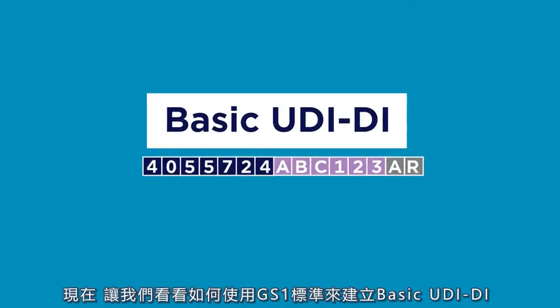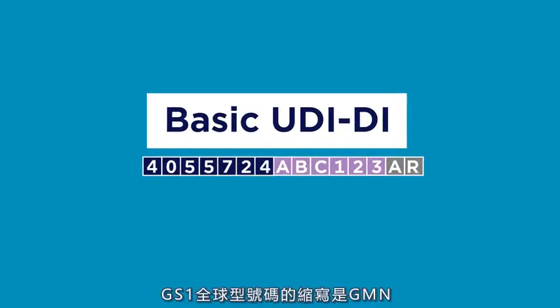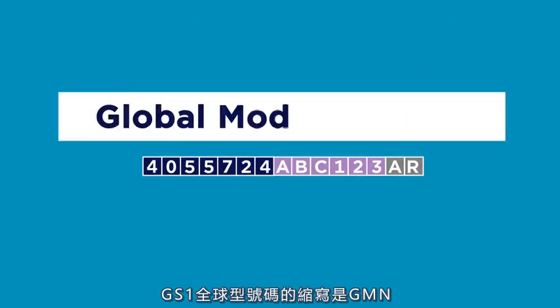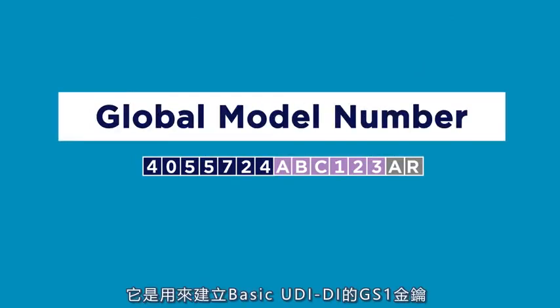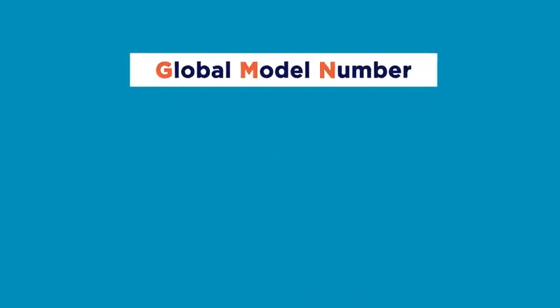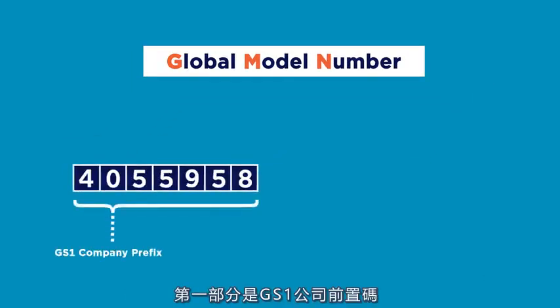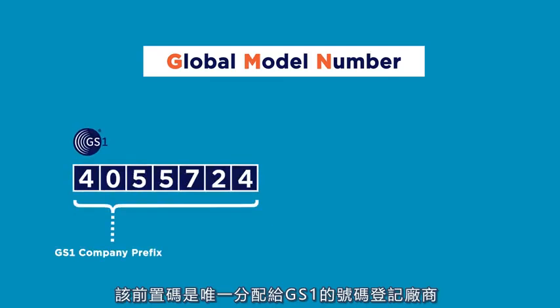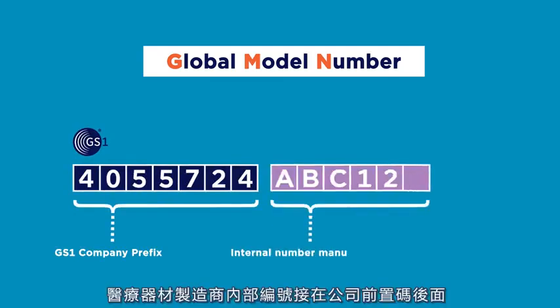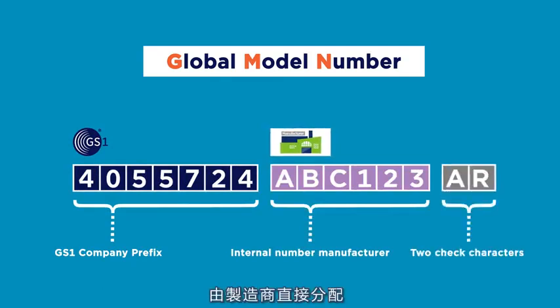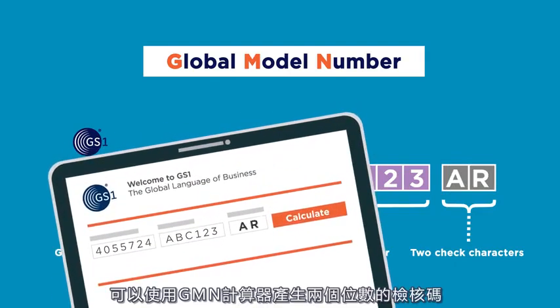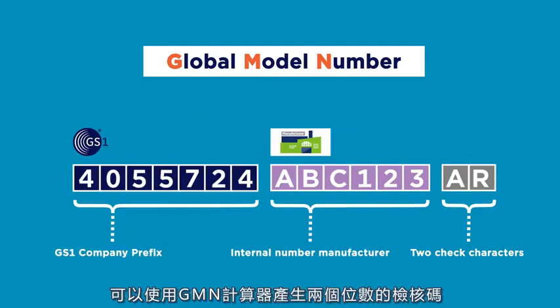Now let's see how you can build the basic UDI-DI with GS1 standards. The GS1 global model number, abbreviated GMN, is a GS1 key which allows the creation of a basic UDI-DI. The first part is the GS1 company prefix, which is uniquely assigned to a GS1 member company. The manufacturer internal number for that group of devices follows, which is assigned directly by the manufacturer. At the end of the GMN, there are two check characters, which can be generated using the GMN calculator.